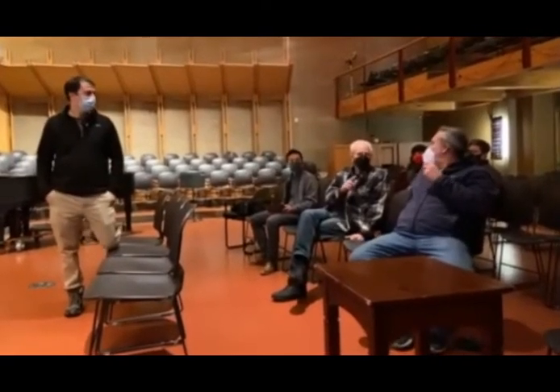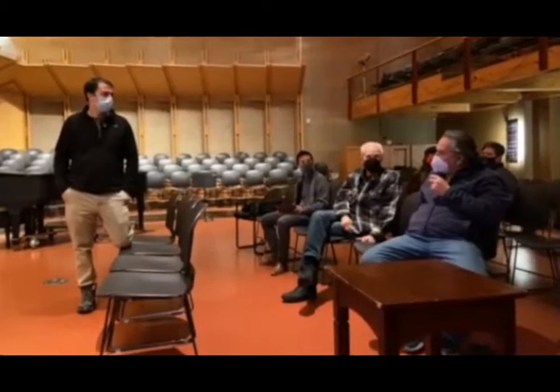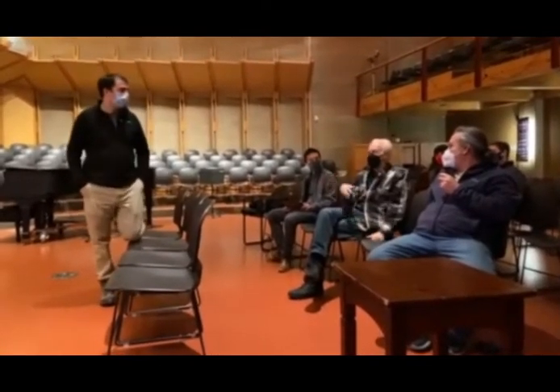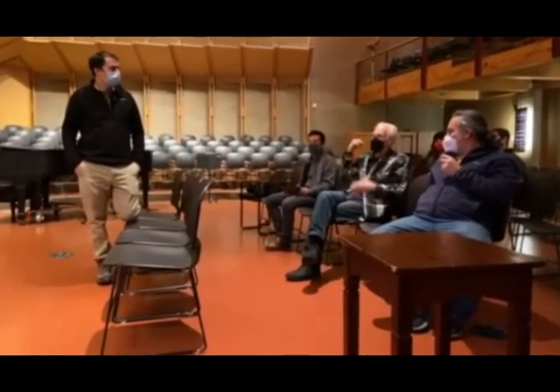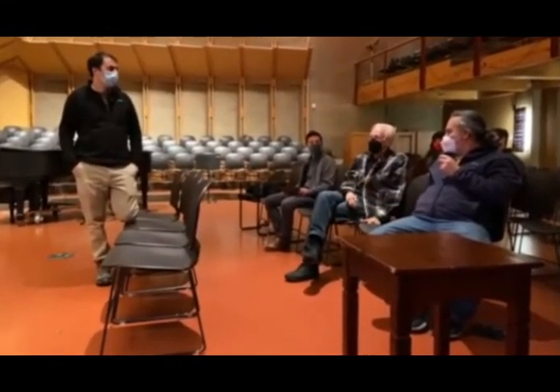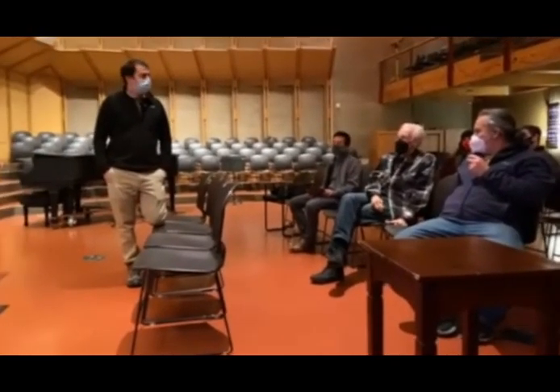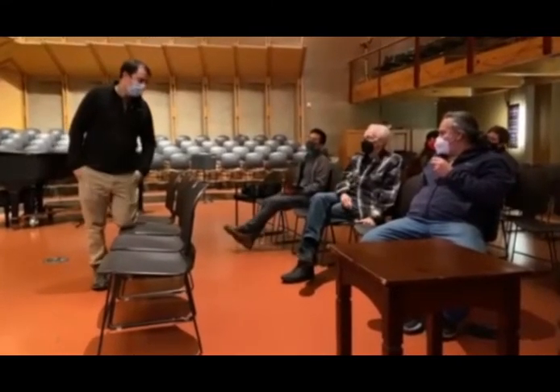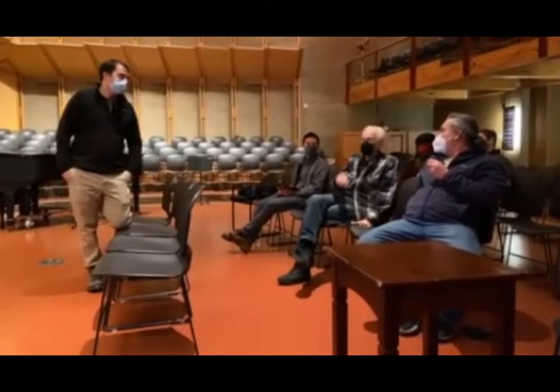That's hard to keep up with. Well, you might want to mention the compressor shutting down for no obvious reasons. I know you've said when there's a big change, a thermal change or a seasonal change, then this could be a headache for Tom. He comes in and they're shut down and there's no obvious reason. Maybe it's the multi-stacks that are not well controlled, internal systems, whatever. Yeah. But this has been an ongoing headache. It's better now, but it's still not good.